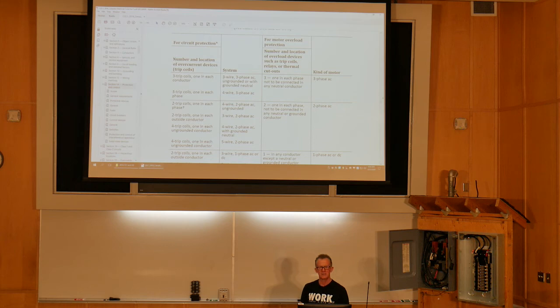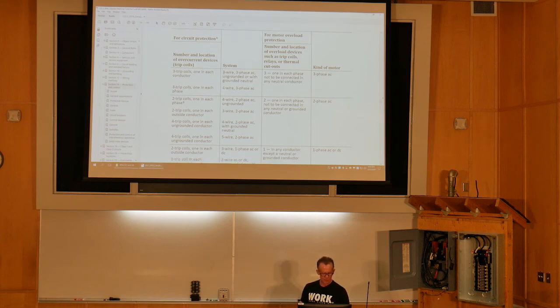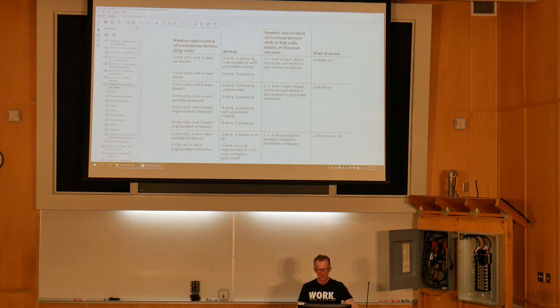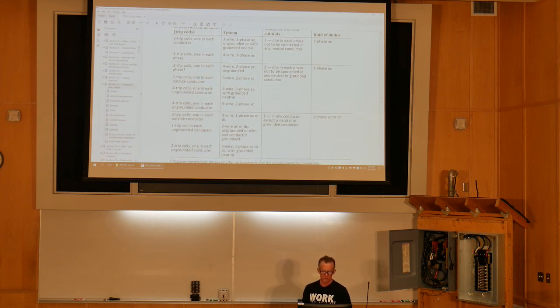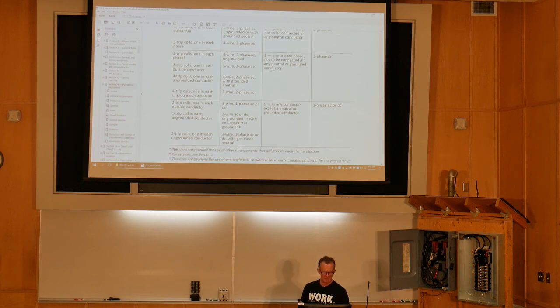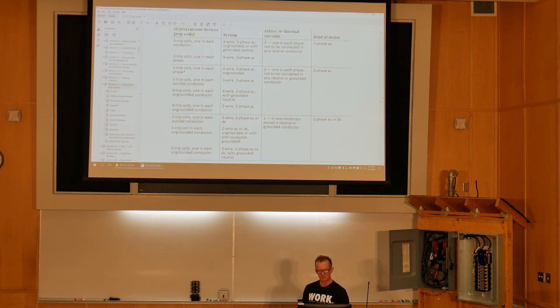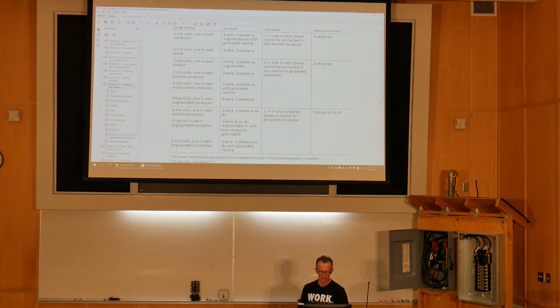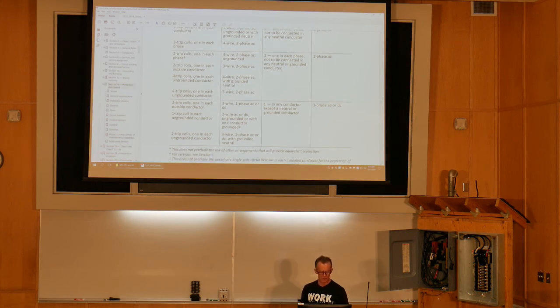1 trip coil in each ungrounded conductor. 3 trip coils, 1 in each phase of a 4-wire, 3-phase AC system. The middle one here, 4-wire 2-phase: we don't see the 2-phase system anymore. I've never seen it in my 20 years in the field, so I doubt you guys will run into it. We can really just skip that. Up here we have the 3-phase, the 2-phase in the middle, kind of obsolete in this day and age, and down here single phase.